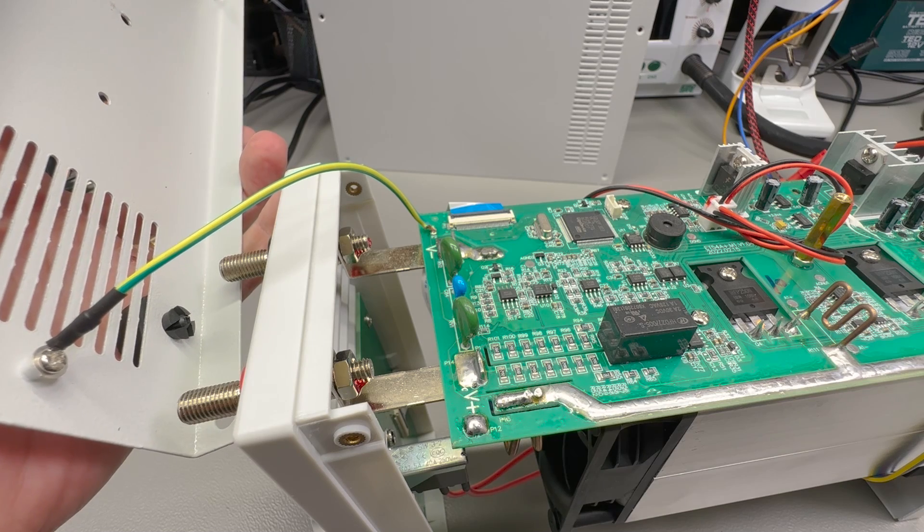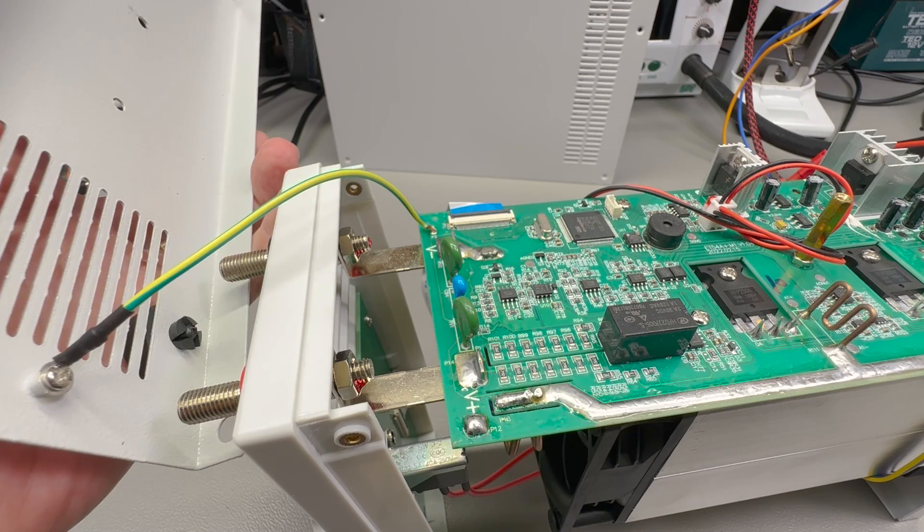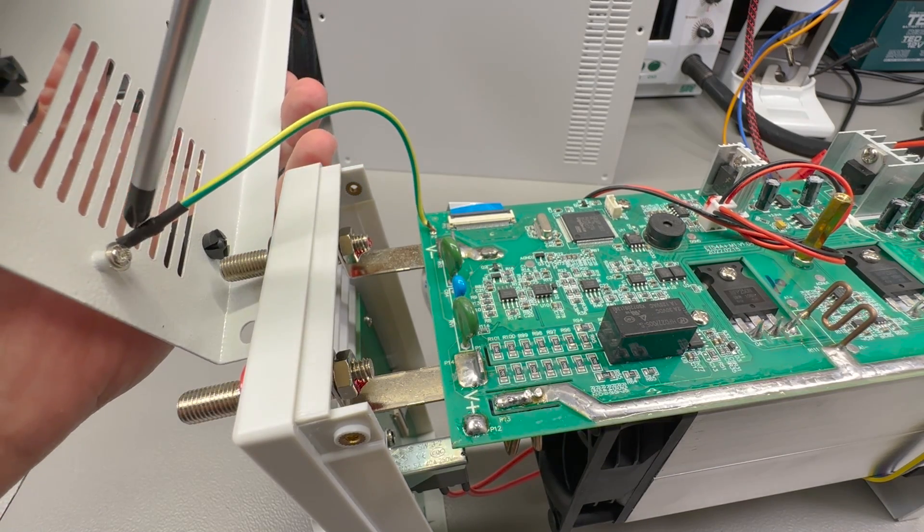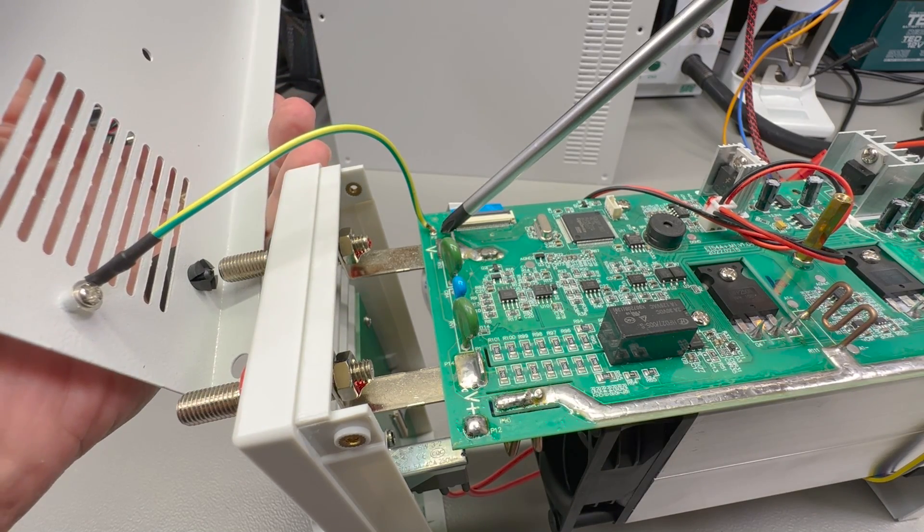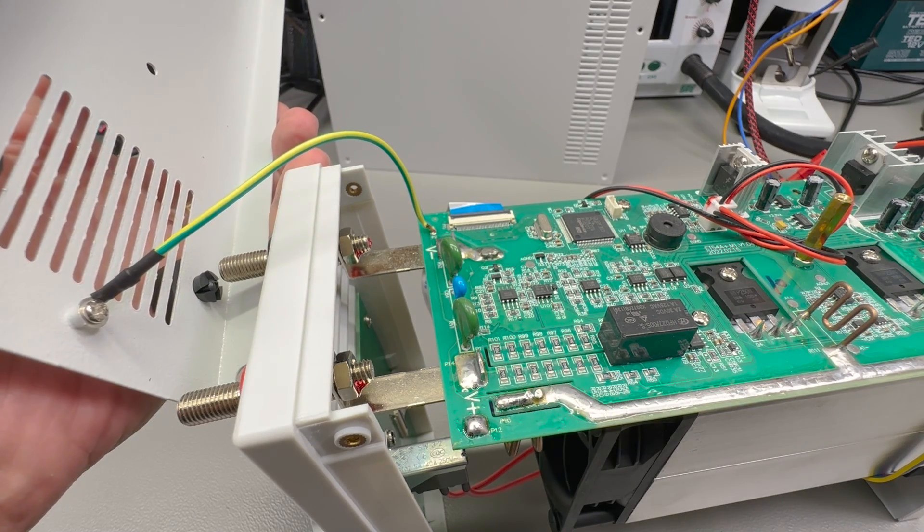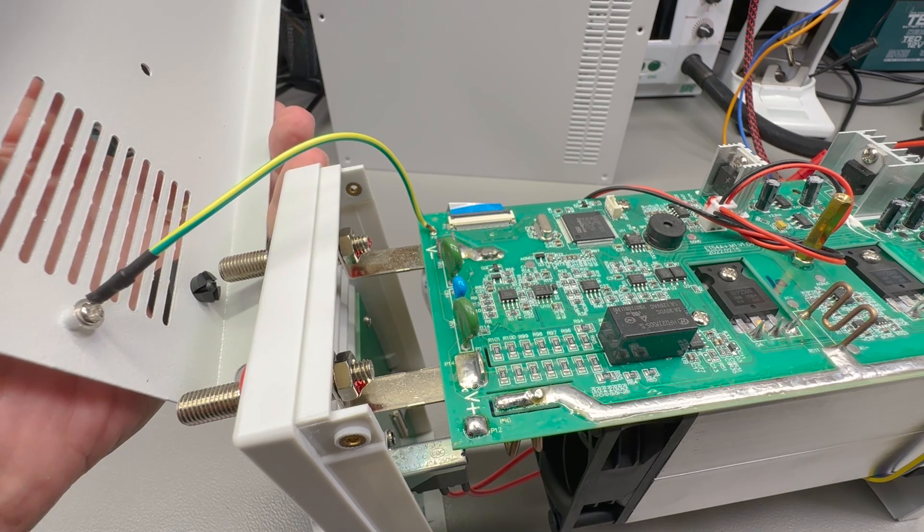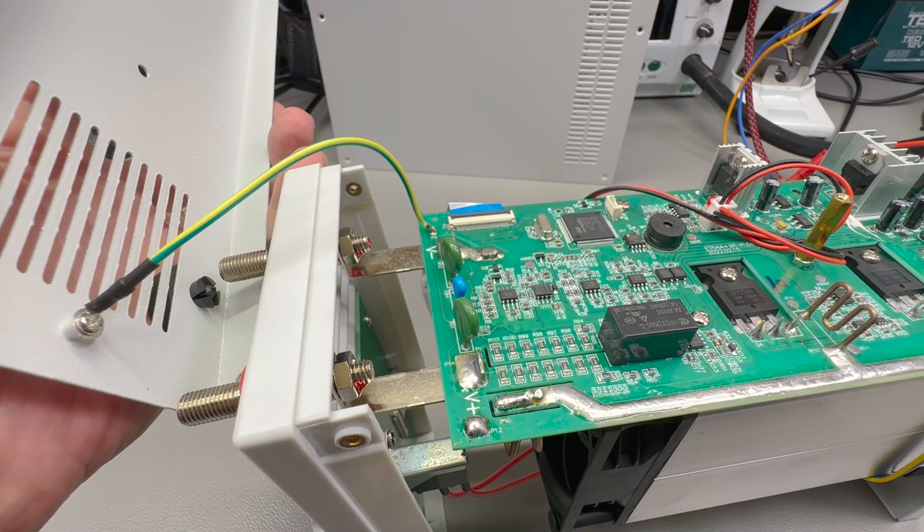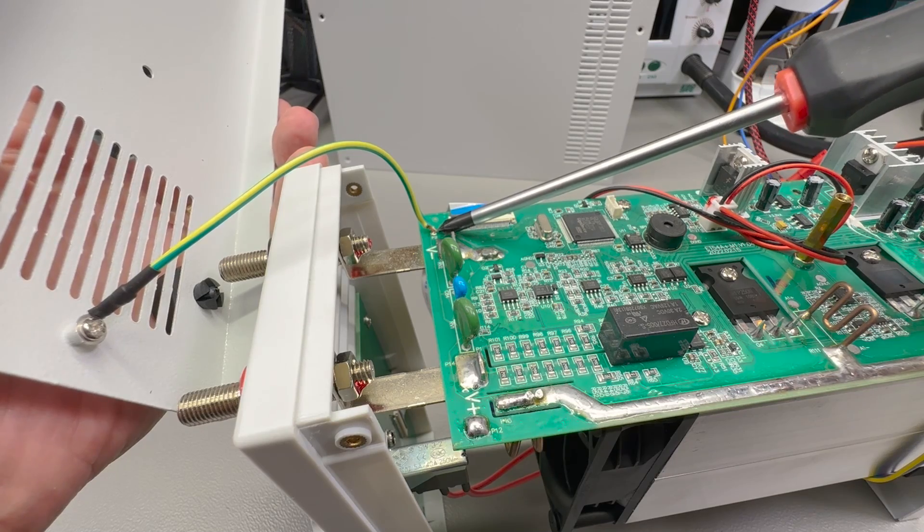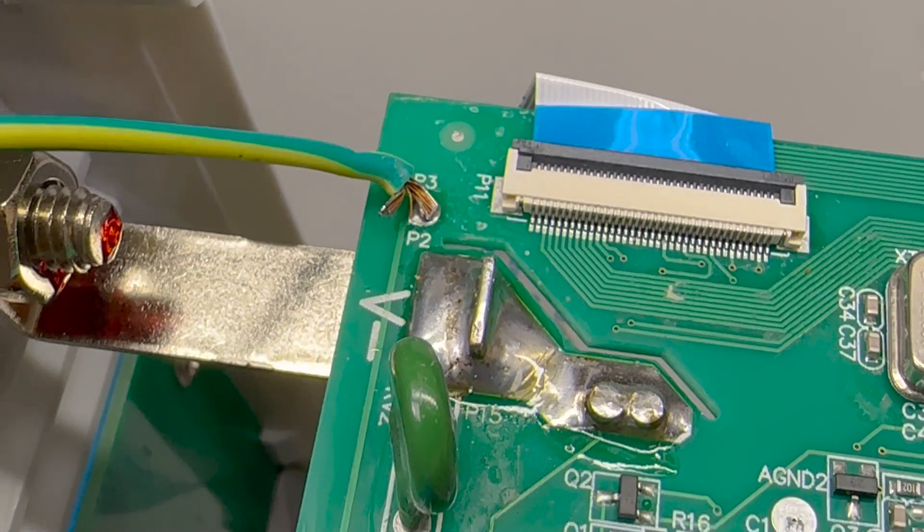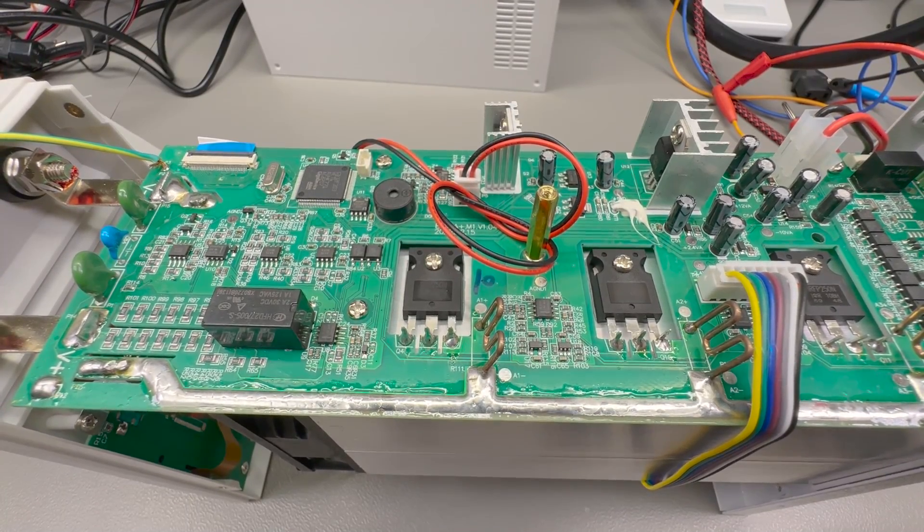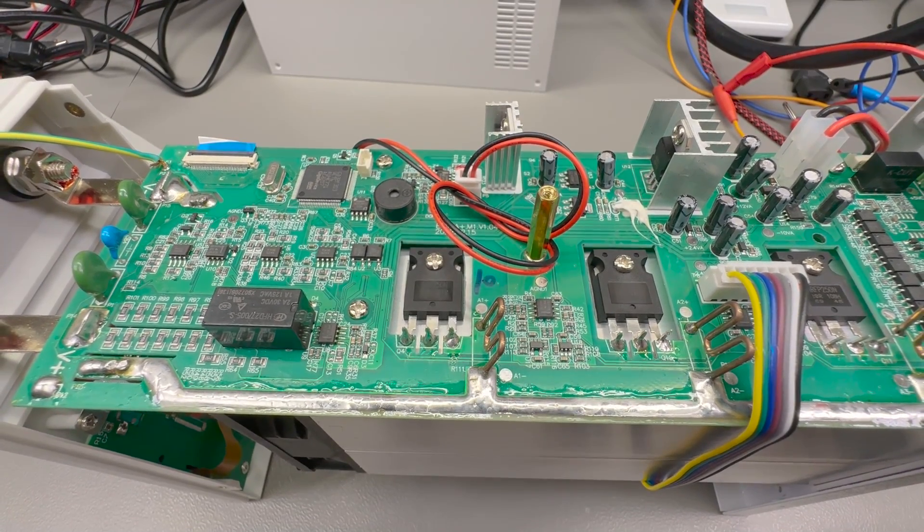And let me show you why we have these strict rules about electrical safety, specifically earthing with these metal enclosures. Take a look at this secondary earth connection which is connected to the enclosure and then goes through the PCB through this very thin line back to the main earth connection. Now there's a lot of stuff that can go wrong on the PCB to interrupt that earthing before it gets to the enclosure, and then there is soldering here, which is forbidden. And why is soldering forbidden on the earth connection? Well take a look at this soldering—it's already three quarters of the way disconnected. So build quality is both good with regards to the general PCB assembly but also bad with regards to mains earth wiring and general placement of wires and connectors throughout the system.